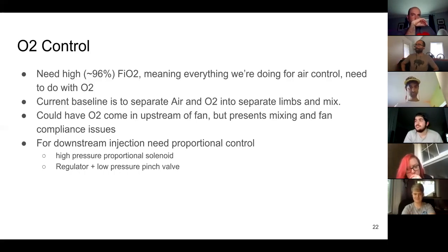I've become skeptical, though I don't know exactly what simulation results we've done to validate that it's infeasible. One issue we looked into was the time averaging of the oxygen mixture: doing 100% O2 at the beginning of the breath and 21% at the end isn't the same as delivering that oxygen consistently over the breath. That really drives us towards an oxygen control valve that can proportionally control the flow rate from the oxygen.